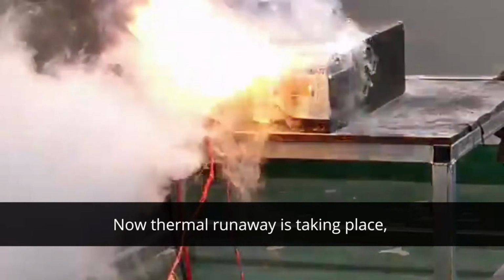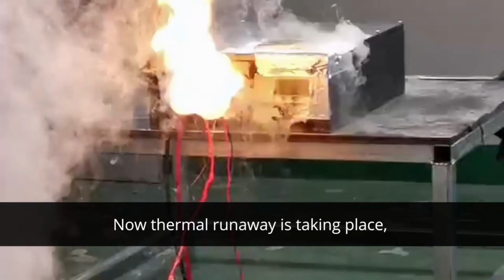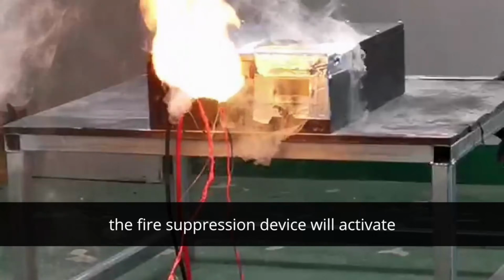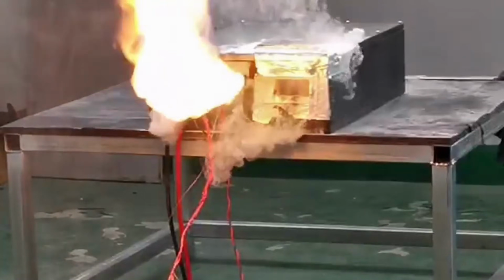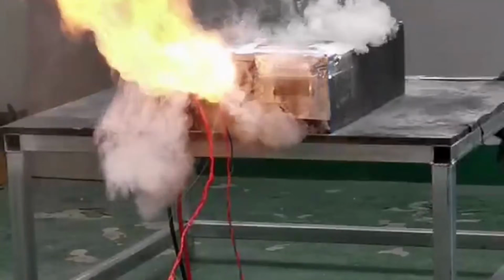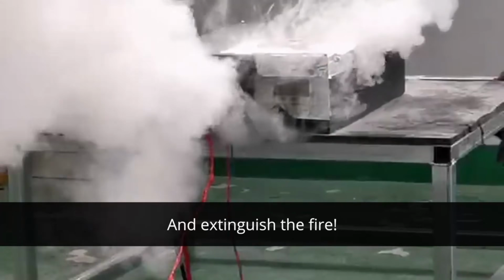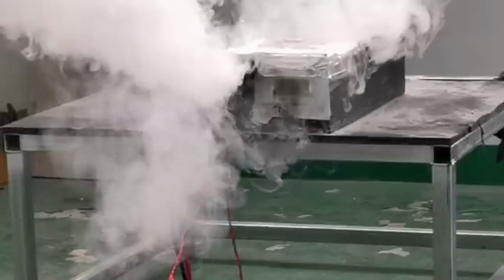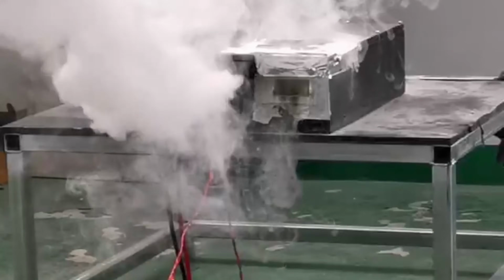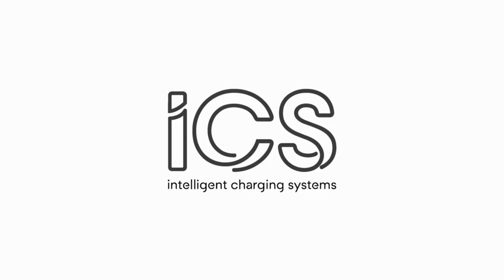We still see quite a bit of smoke coming out. We've now got ignition, so thermal runaway is taking place, and the fire suppression is now going to activate and put that out to make sure there is no damage beyond the local area of the battery itself.